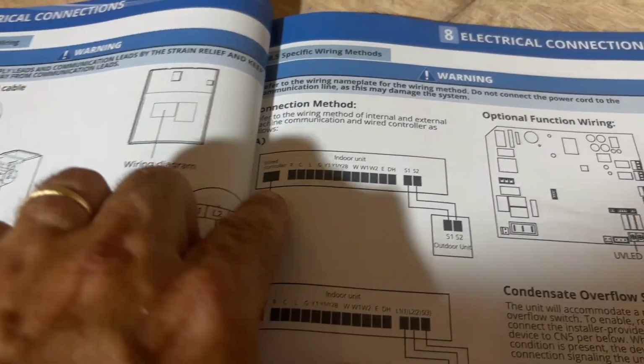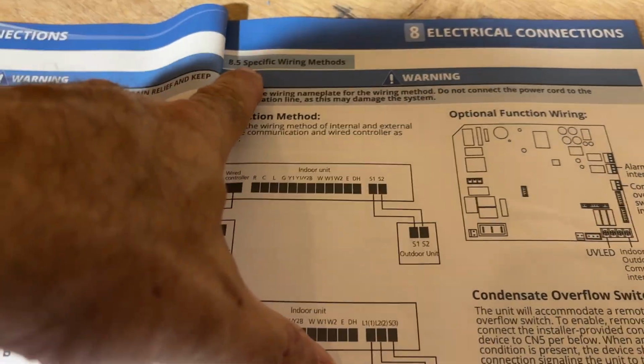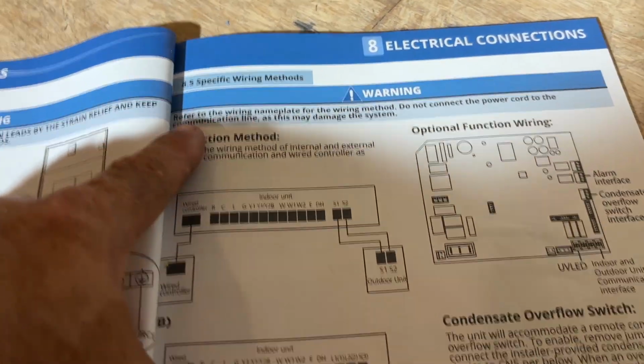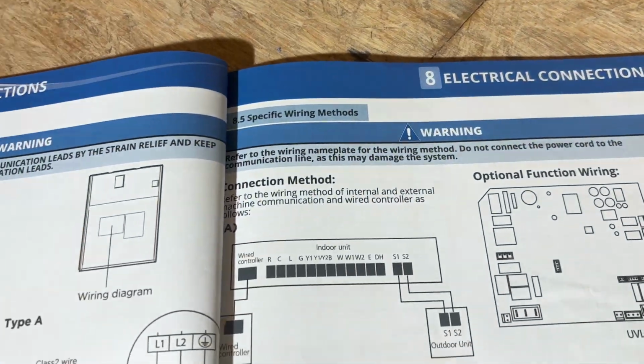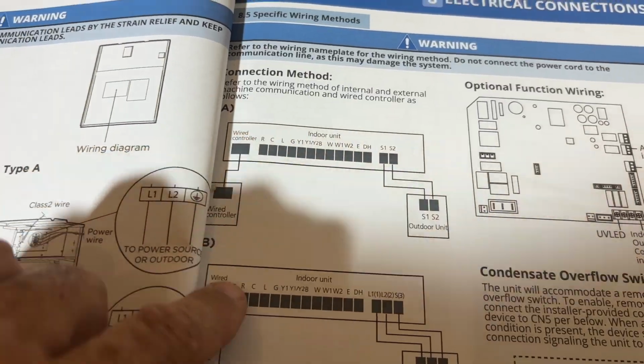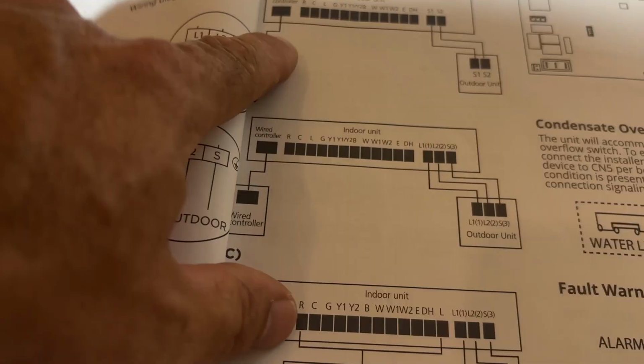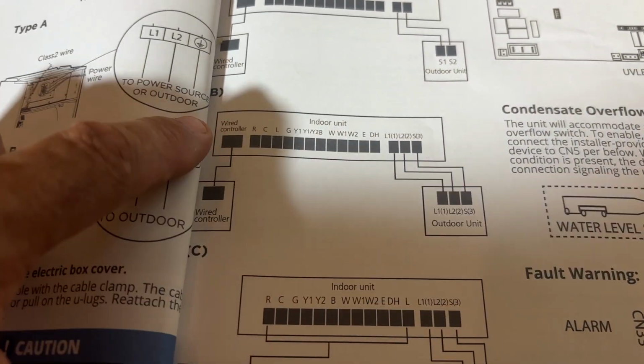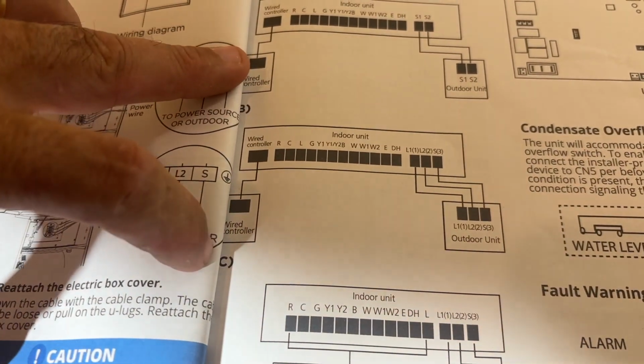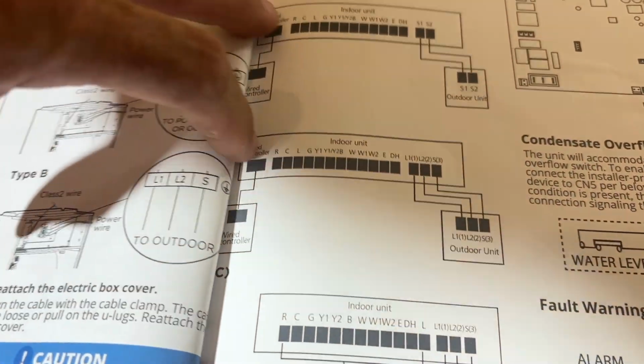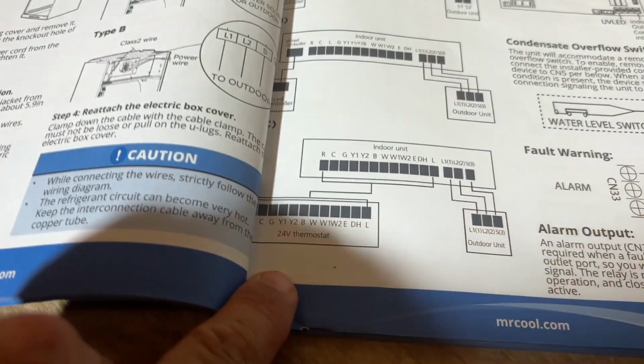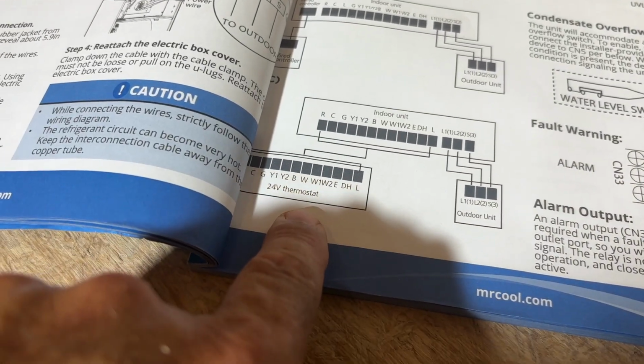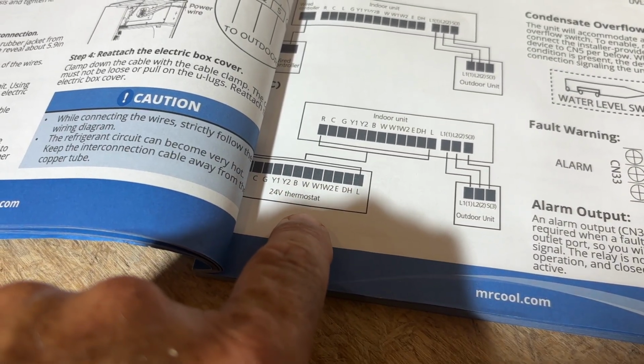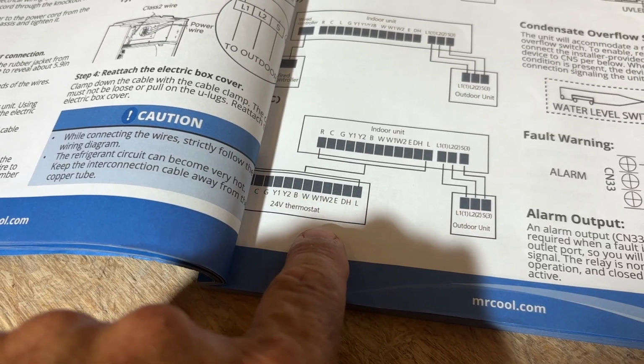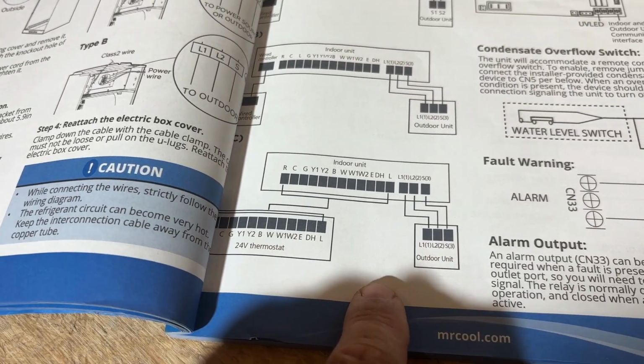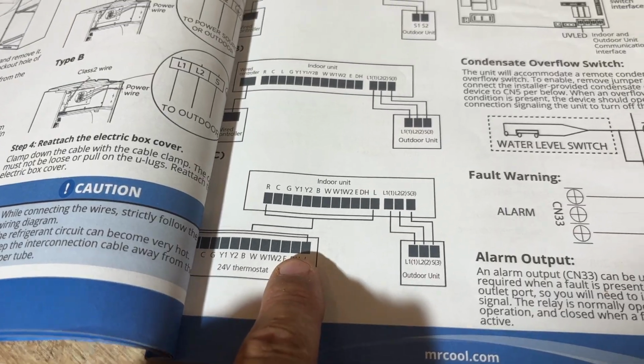Now we're into the manual here as far as specific wiring methods. So chapter 8.5, and it goes through your different options. You have 3 different configurations, A, B, and C. If you're going to use the wired controller that comes with the unit, these top 2 would apply to you. And this bottom one, if you're going to use a 24 volt system or a third-party thermostat, which we're using, the Nest 4th generation thermostat, this will be our configuration.